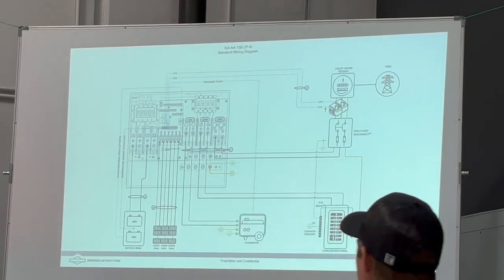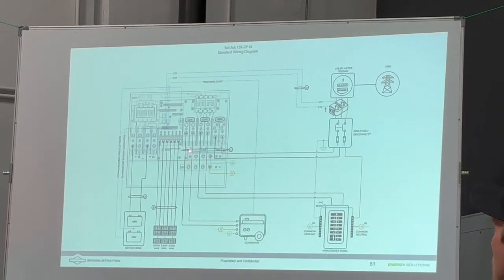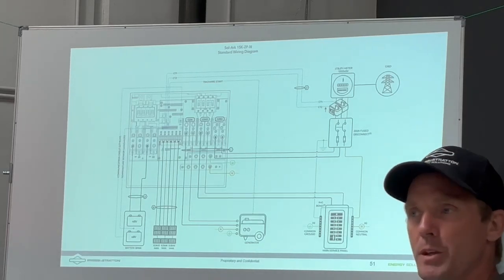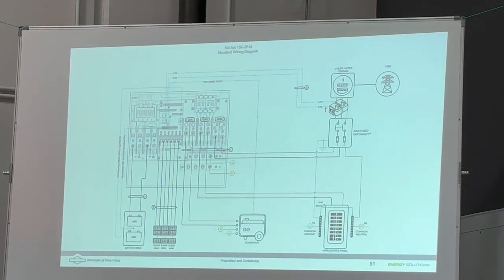Right here I'm showing you a generator being brought in through the gen port on the inverter. If you do it this way, you're limited to 80 amps continuous from the generator. So 80 amps is 19 kilowatts. I mean, that's enough for most houses. But let's suppose you've got a 26K generator on that transfer switch, or maybe you have a bigger generator than that. Maybe you have a 35K, right? You want to be able to pull all the power off the generator.